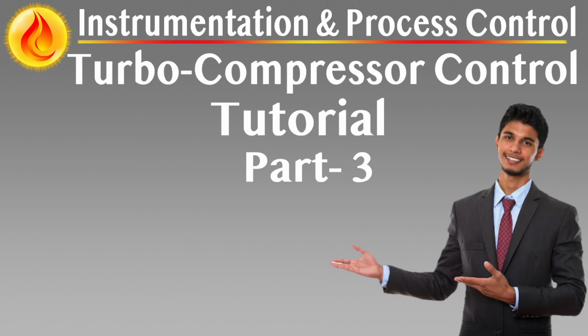Controller decoupling. The TCCS is designed with a fully decoupled control architecture, ensuring that individual control loops, such as anti-surge, performance, and load sharing, operate without interference. This strategy is critical for preserving control performance, minimizing oscillations, and avoiding unintended interactions.